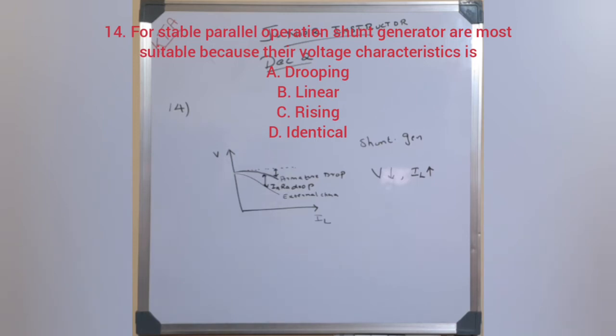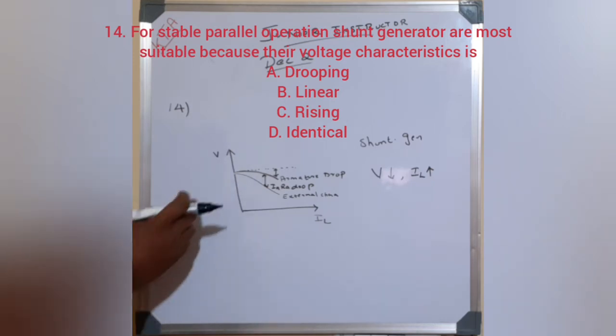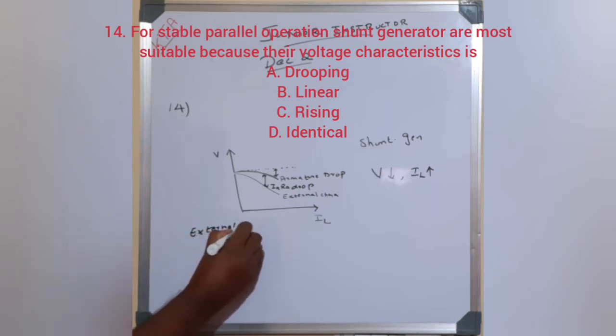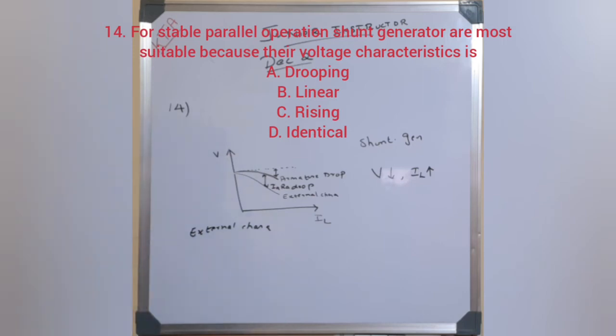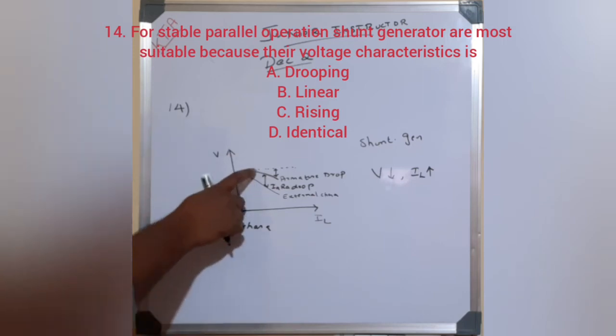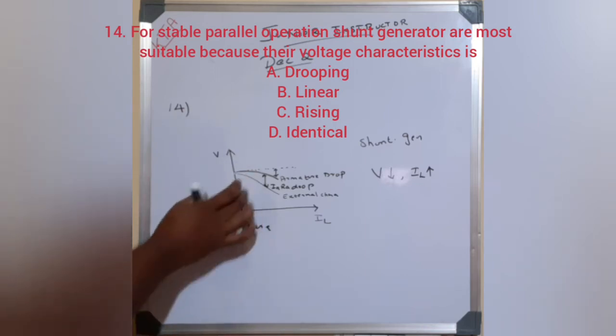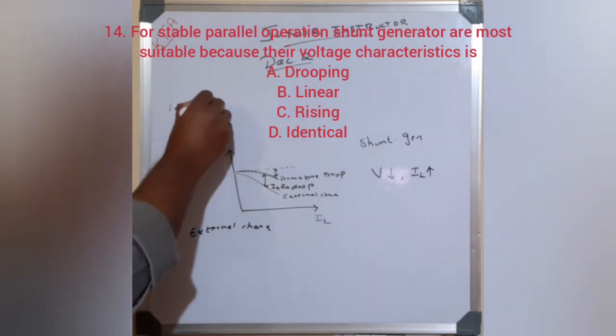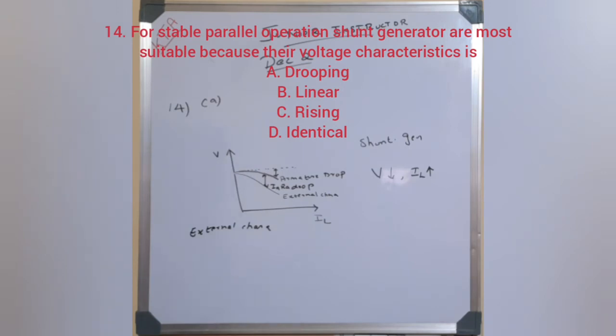The answer is 'drooping.' The series generator has a rising characteristic. For the shunt generator, the external characteristic — the V versus IL plot — shows a dropping terminal voltage as load current increases due to armature drop (IA × Ra). Because of this drooping external characteristic, the shunt generator is stable for parallel operation. Option A is correct.